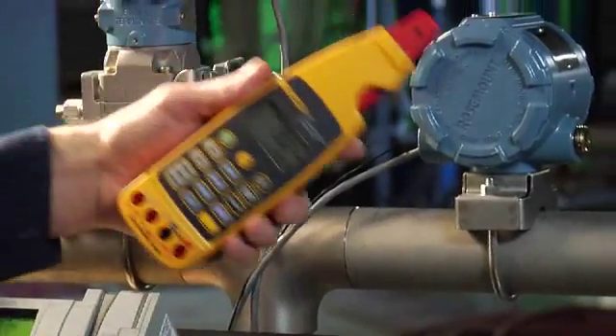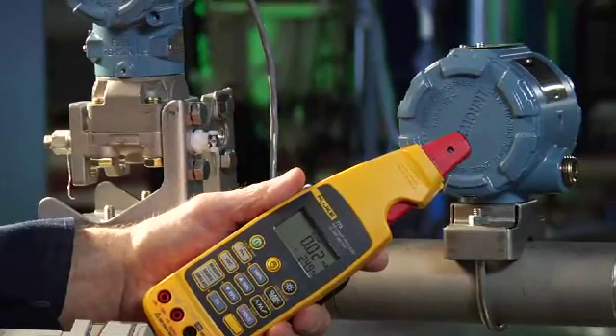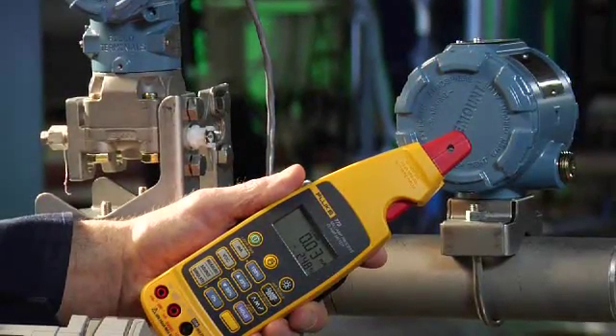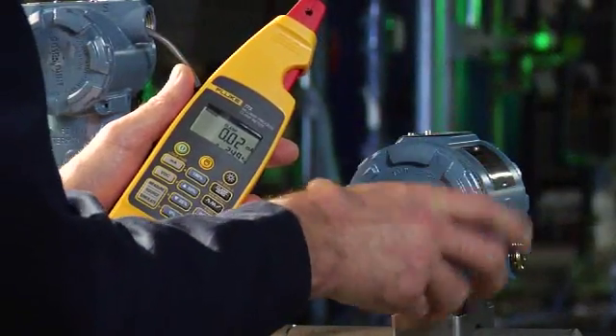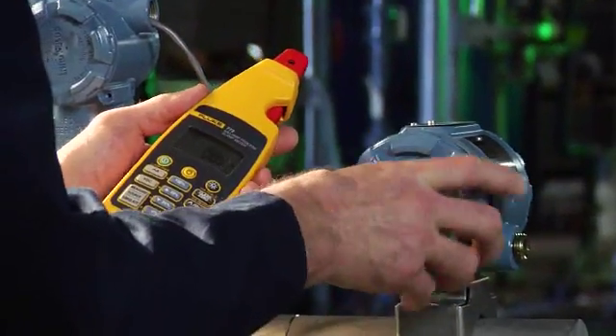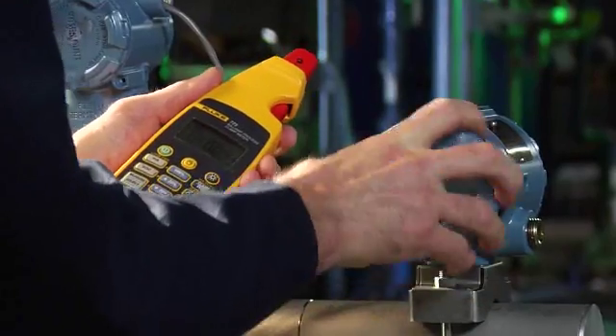Once the bad signal is found, you can then use the milliamp loop troubleshooting capabilities of the 773 to isolate the fault. To troubleshoot the loop, you need to access the signal wires. Remove the cover on the transmitter and find the signal wires.